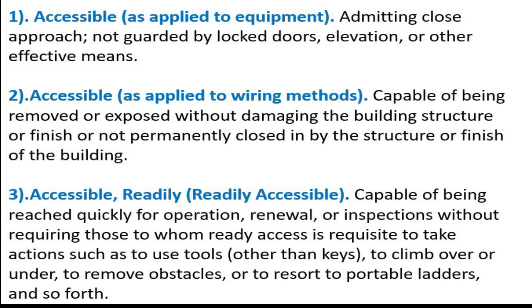Accessible, readily (readily accessible): Capable of being reached quickly for operation, renewal, or inspections without requiring those to whom ready access is requisite to take action such as to use tools other than keys, to climb over or under, to remove obstacles, or to resort to portable ladders, and so forth.